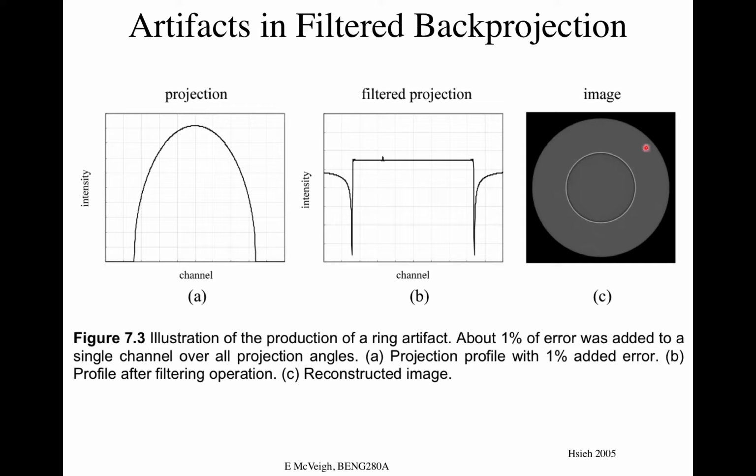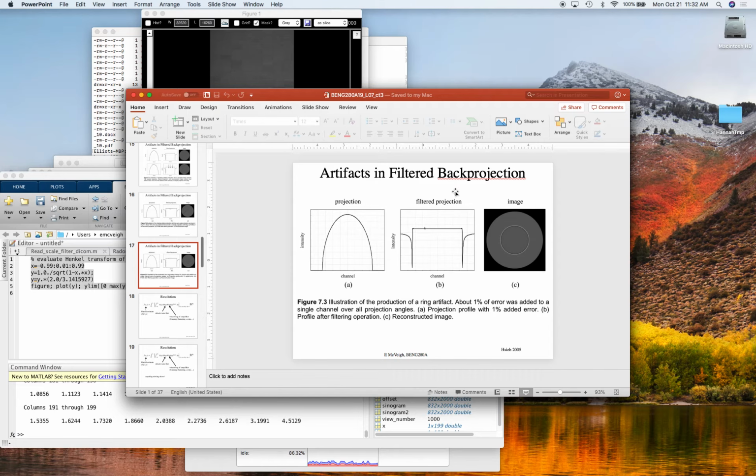Yeah, normally they're called phantoms, and normally it's a Perspex cylinder, and so it has its own Hounsfield unit on the edge, and you just live with it. I could bring in some pictures of phantoms that are used each day. The first thing they do in the day is put a phantom in and scan it with a couple of different protocols, and then they'll take an air scan. You can imagine an air scan is a very useful thing in that it gives you the relative amplitudes of those data.